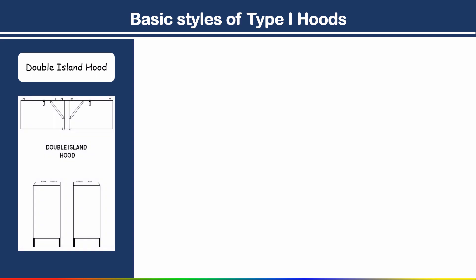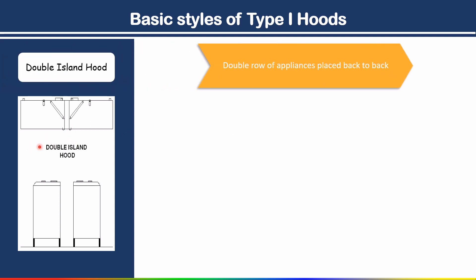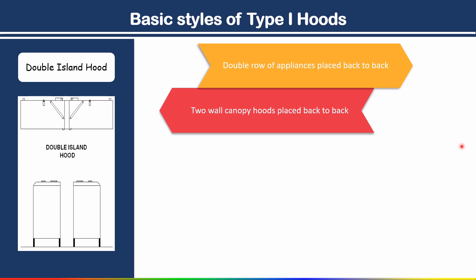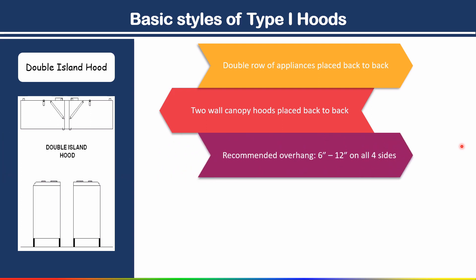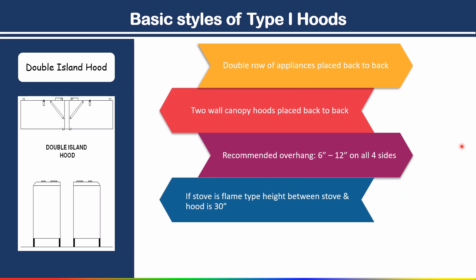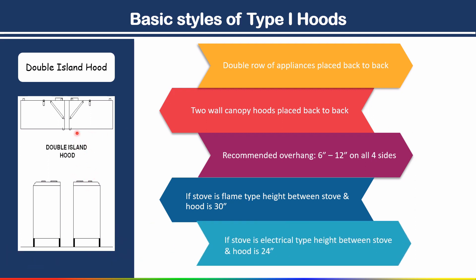Next in basic styles of type 1 hood is the double island hood. In a double island hood, appliances are placed back to back — a double row of appliances back to back. Two wall canopy hoods placed back to back. Recommended overhang for the double island hood is 6 to 12 inches on all four sides. For height between stove and hood: if the stove is flame type, maintain 30 inches; if electrical type, maintain 24 inches.